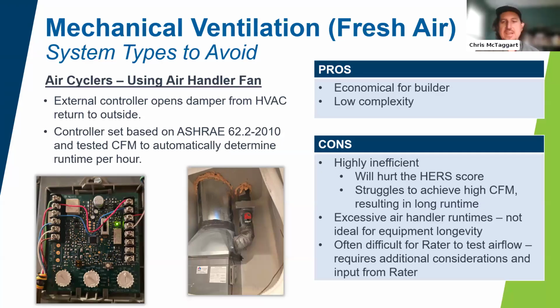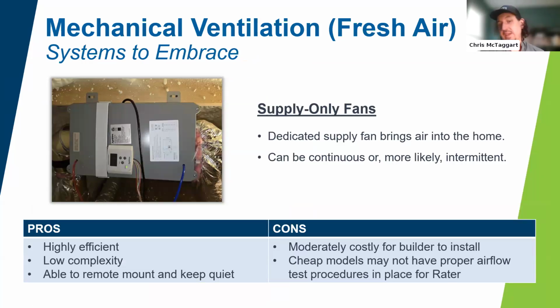And it's hard to test the airflow and get it right. You're relying on negative static pressure to be able to bring in a specific amount of air. And you'd be surprised at how oftentimes I've seen very little airflow coming in out of these systems. So it's not predictable. You could get a supply-only fan, like an actual inline fan that's more dedicated. They're pretty efficient. They're low complexity. They're a little bit extra money, but not that much. Depending on the model they use, it may or may not have the ability for a rater to test it easily. But honestly, I would consider this as another option.